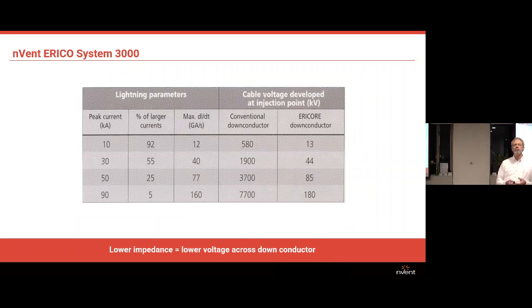This table just indicates the performance of the down conductor. The right-hand column shows the cable voltage developed at the injection point. Now, in an ideal world, there'd be no resistance or impedance between the cloud and the earth where the lightning current is got rid of, you might say. In practice, when it hits the lightning protection system, there is an impedance between that strike point and the ground.